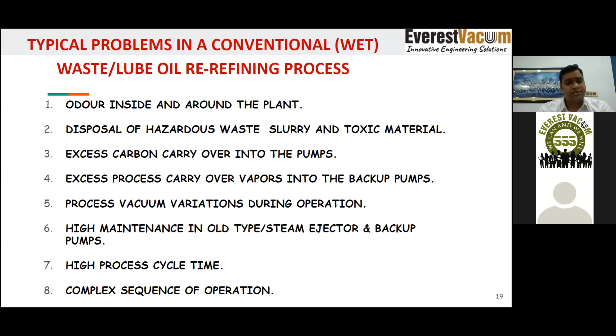So this is the cost benefit analysis after what we have discussed so far on the vacuum system and the process. This is also on the same case study that we showed you earlier. The process is waste oil re-refining. Distillation is under vacuum. The pumping capacity we are offering here is 10,400 meter cube per hour. The vacuum in the process is 0.5 torr absolute. The vacuum system we have here is OilSys 2.5, and the old type of system with which we are comparing is a 3-stage steam jet ejector.